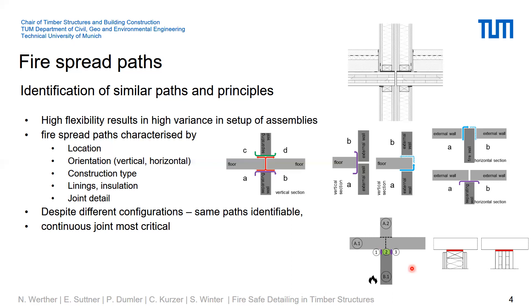Looking more closely at these aspects, you can identify similar paths, similar ways, and similar principles which result in the same methods. For instance, straight joints or continuous gaps in walls or floors result in the same method, as shown here. Most critical is always the straight joint to other compartments, which must be tightly jointed to avoid fire spread and smoke spread.